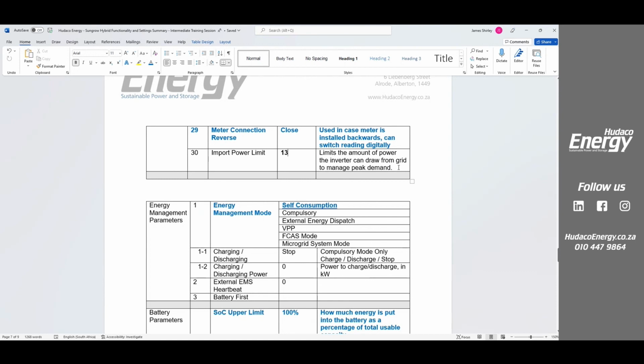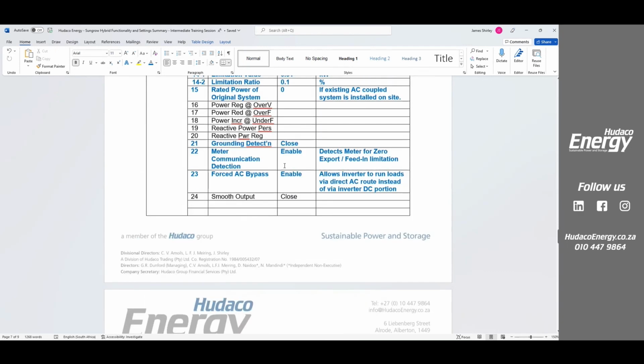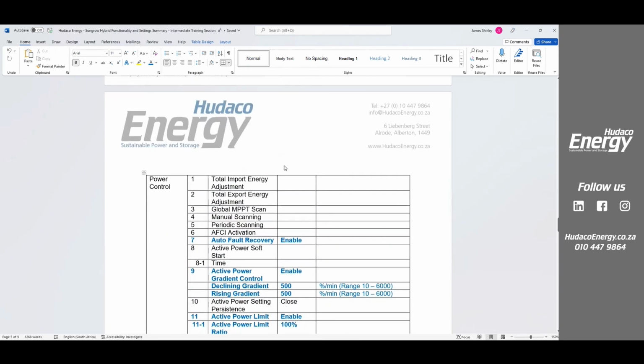This is again to protect if cables are too small, or if you want to do demand management. So maybe your client says, well, if I'm allowed to import 6 kilowatts, if I go over that at all, I'm charged an extra fee. You can set a limit to the amount of energy that you import here. The default is 13, so it's that 13 kVA, and that's protected by a 63 amp breaker on a 10 mil cable. If you've got any questions on any of these settings, by the way, please ask me.